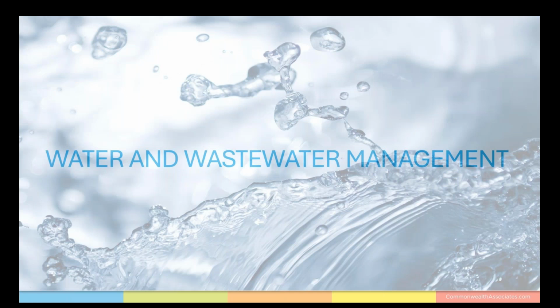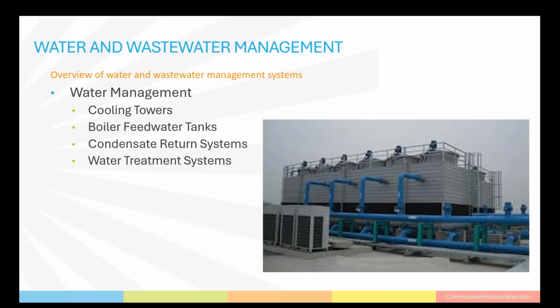Now we're going to move into water management. Water management and layout considerations. Position cooling towers to minimize plume drift and to ensure adequate airflow. We want to place boiler feed water tanks near the boiler with consideration for gravity feed and pump suction.